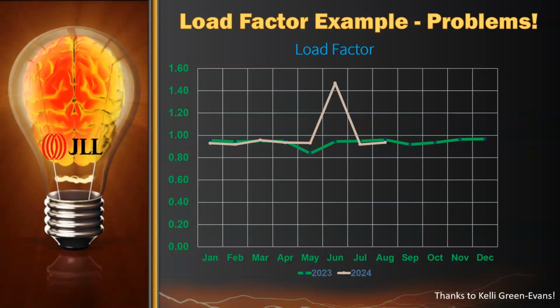It very much does affect the kW reading, the kilowatt hours. That harmonic does affect that. The kVA it really doesn't affect. The way the meter reads it, it's an average, and it kind of misses all that stuff. It's just not made to do that.